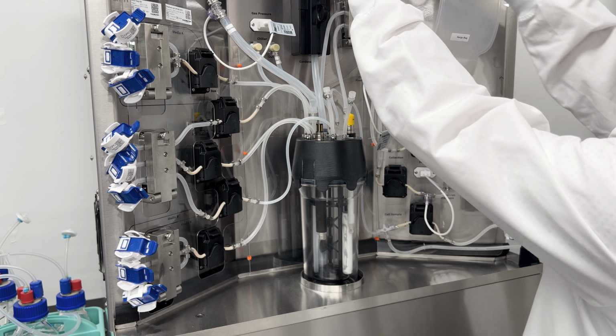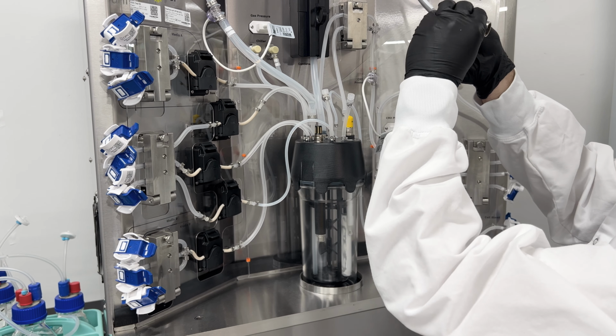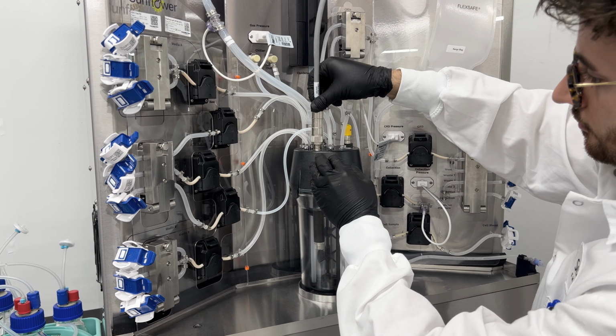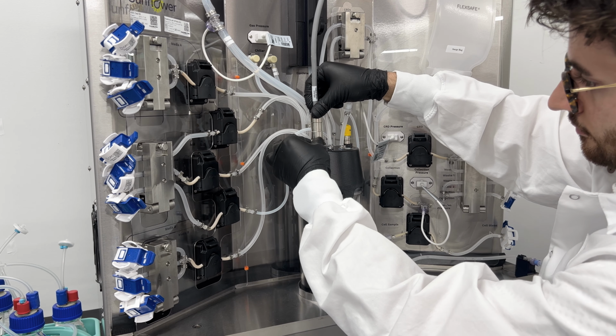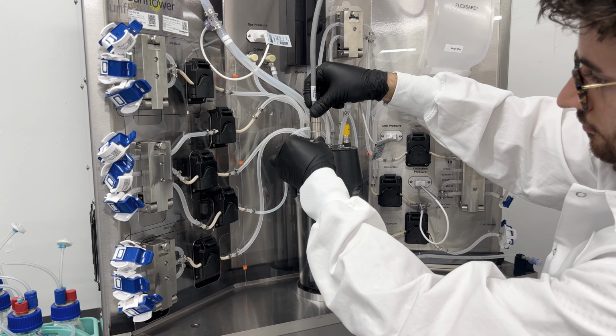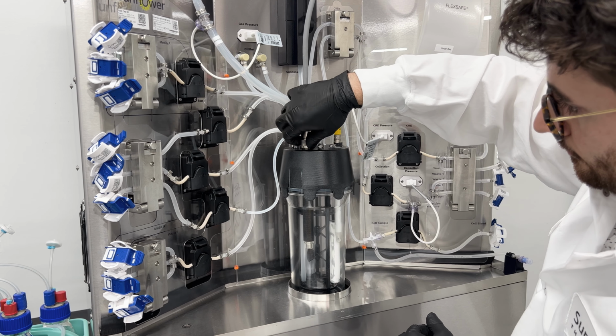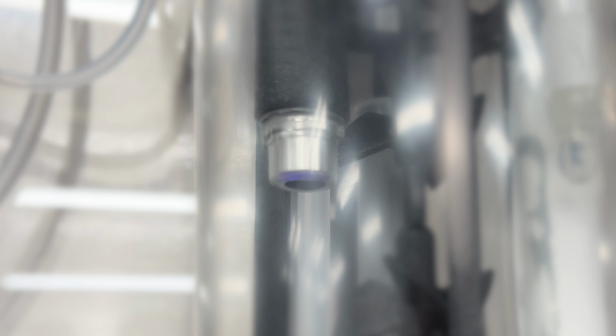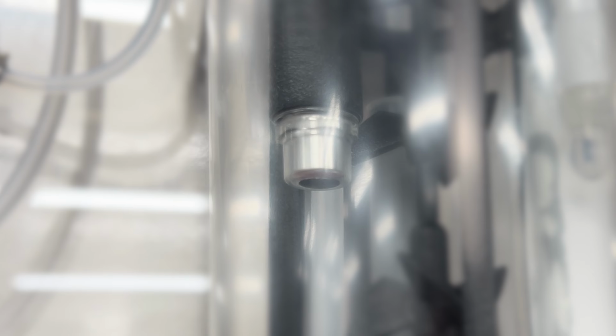Now we can take the DO cable connector and place it onto the DO probe, turning it until the keyed connection catches onto the connector on the probe. Tighten the threaded collar of the cable onto the probe's threaded connector until it's finger tight. A flashing blue light at the end of the probe will indicate that the cable is properly connected.